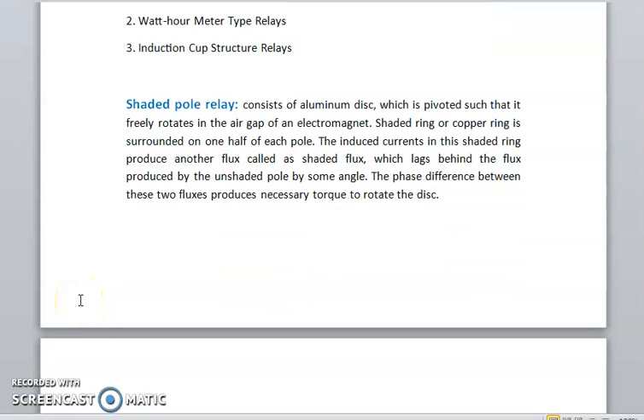Shaded pole relay consists of an aluminum disc which is pivoted such that it freely rotates in the air gap of an electromagnet. Shaded ring or copper ring is surrounded on the half of each pole. The induced current in this shaded ring produces another flux called the shaded flux, which lags behind the flux produced by the unshaded pole by some angle. The phase difference between these two fluxes produces the necessary torque to rotate the disc.